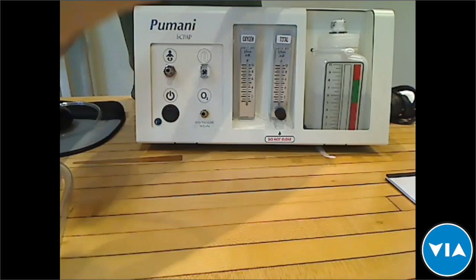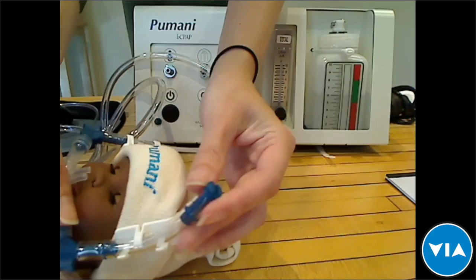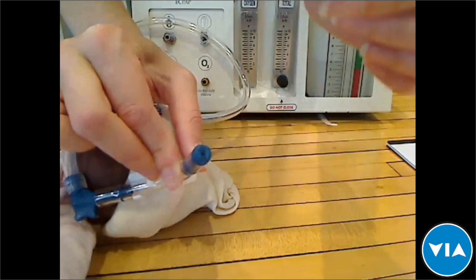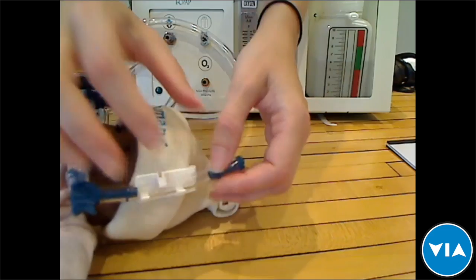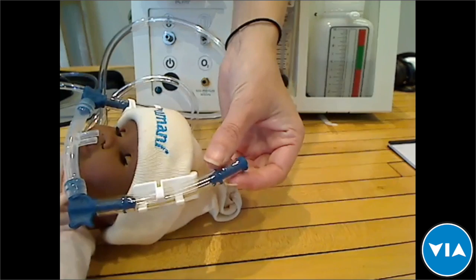I can also just show you on the doll here that there is, at the end of the tubing here, so we have the tubing from the machine to the baby. And on this end here, we call this the end cap. And there's a small hole here. So this is the only point where there is a small leak in the system. You may not be able to see this on the screen, but there's a very small hole, and that allows for any additional exhale to release from the tubing. So we've done a lot of testing on this piece in particular, and this ensures that the pressure is still stable at the nasal prongs, but it allows for exhale to release at the end cap.